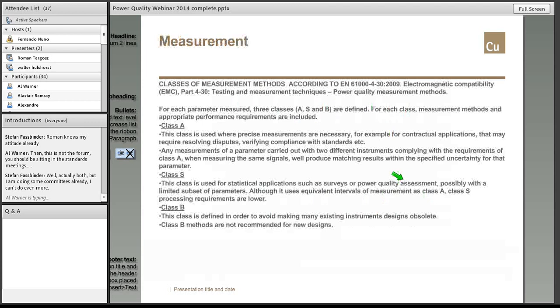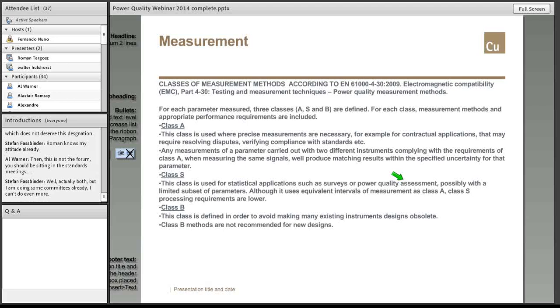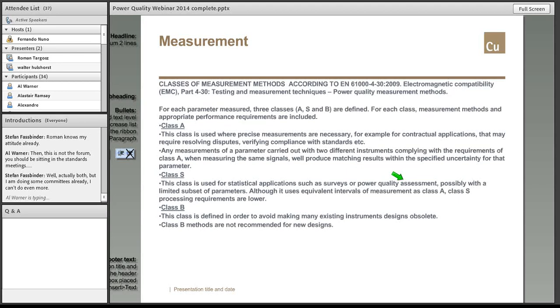Next one is about measurement. It is not particularly part of EN 50160, but I think it's worthwhile to know that we've got class A equipment because it verifies compliance to EN 50160. And it is class A which has sampling of 0.2 seconds, then aggregation of 3 seconds, 10 minutes, 2 hours. So it is basically the equipment which should be used for all contractual issues. Then we've got class S, which has the same averaging principle, but should not be used for contractual purposes. And then we've got class B, which is steadily withdrawn, and it's rather obsolete equipment.